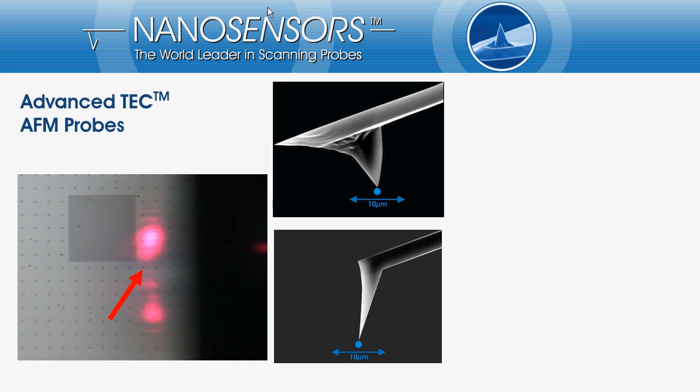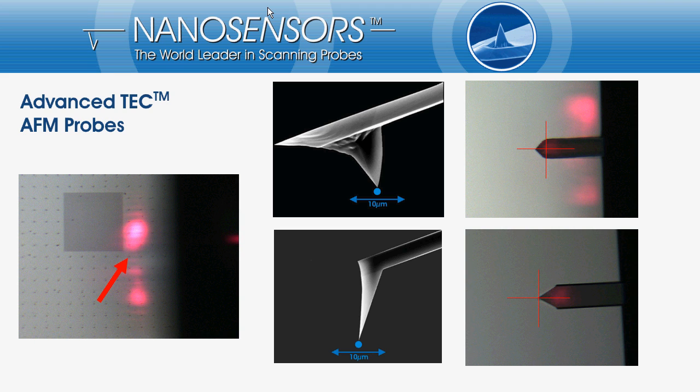To illustrate the problem I took two side view SEM images — a standard silicon tip and an Advanced TEC probe — and combined them with a sketch of our point of interest and the size of the scanning window. Looking through the AFM's microscope we see the back side of the cantilever and can place the marker at those points where we believe the tip might be for the standard probe, and where the tip effectively is for the Advanced TEC probe.